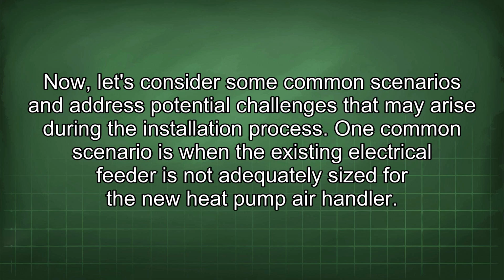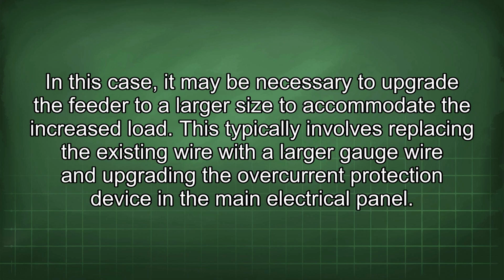One common scenario is when the existing electrical feeder is not adequately sized for the new heat pump air handler. In this case, it may be necessary to upgrade the feeder to a larger size to accommodate the increased load. This typically involves replacing the existing wire with a larger gauge wire and upgrading the overcurrent protection device in the main electrical panel.